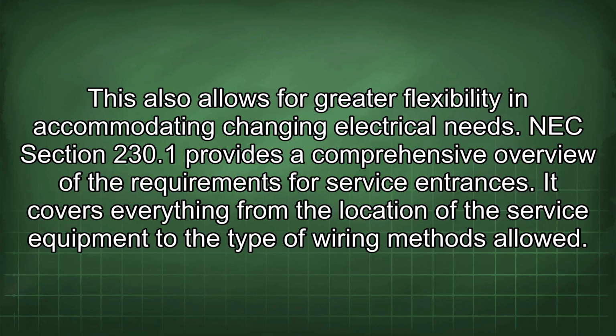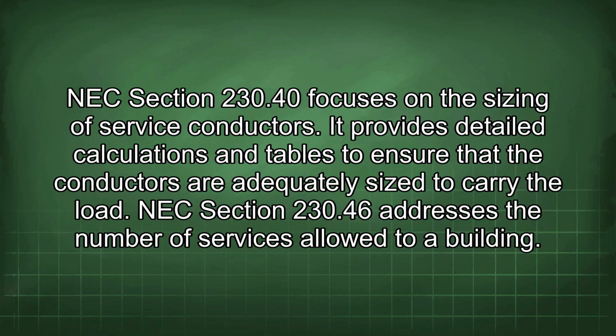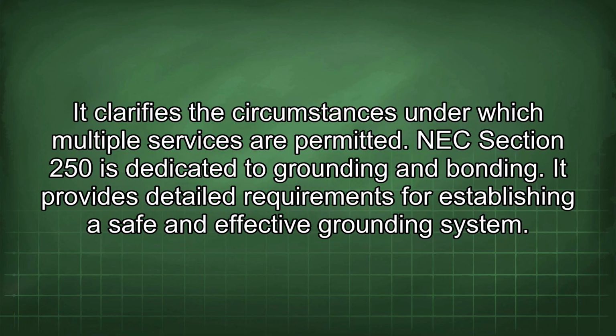NEC Section 230.1 provides a comprehensive overview of the requirements for service entrances. It covers everything from the location of the service equipment to the type of wiring methods allowed. NEC Section 230.40 focuses on the sizing of service conductors. It provides detailed calculations and tables to ensure that the conductors are adequately sized to carry the load. NEC Section 230.46 addresses the number of services allowed to a building. It clarifies the circumstances under which multiple services are permitted.